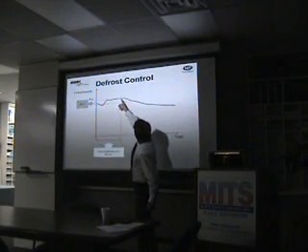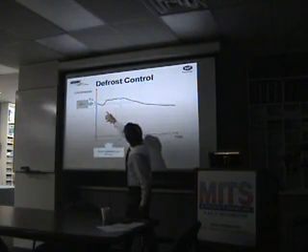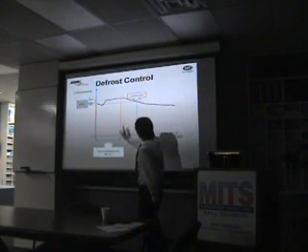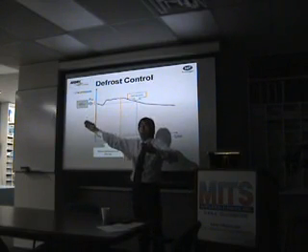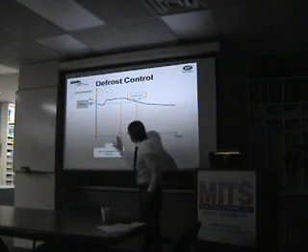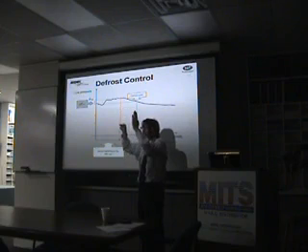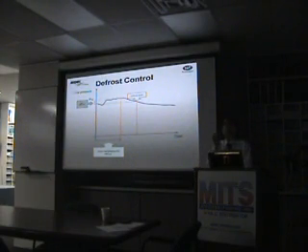the development. If we see the pressure dropping down of more than 0.4 bar, it means we are taking ice on the coil, and so we need to defrost. And this is the frost point. So if it didn't drop for more than 0.4 bars, we keep it going. And then after 660 seconds, we set another set, we check, and if it's dropped 0.4 bar, we do the defrost or not. So in this case, we always know how much ice we have stuck on the coil.